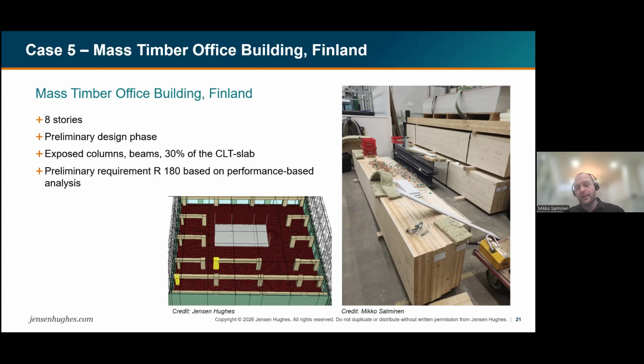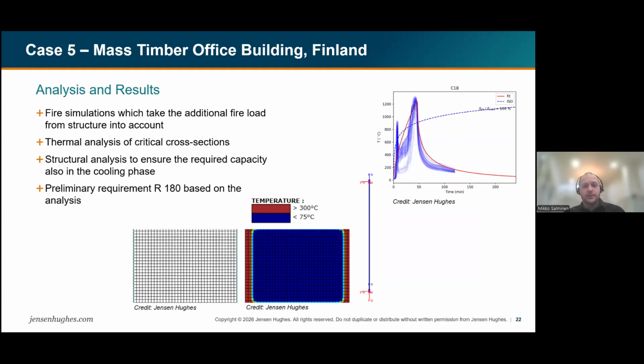Our preliminary requirement for the structural engineer was that he needs to design it to 3 hours. That of course sounds quite a large requirement, but actually the size of the elements was quite large also, so it wasn't mostly a problem because they have quite good inherent fire resistance. So we did those fire simulations, and in this case, you can see from the top right corner the temperatures. They go now over the standard fire curve because of the additional fire load.